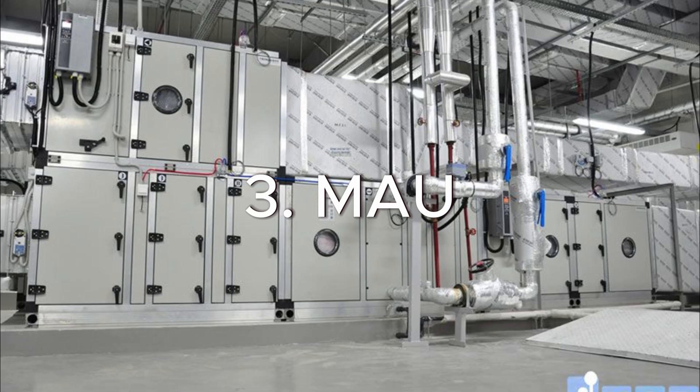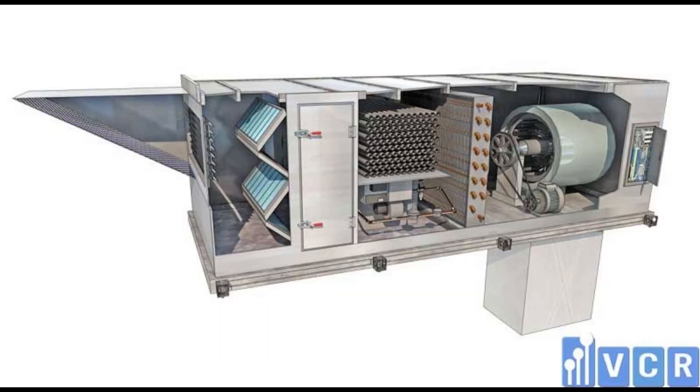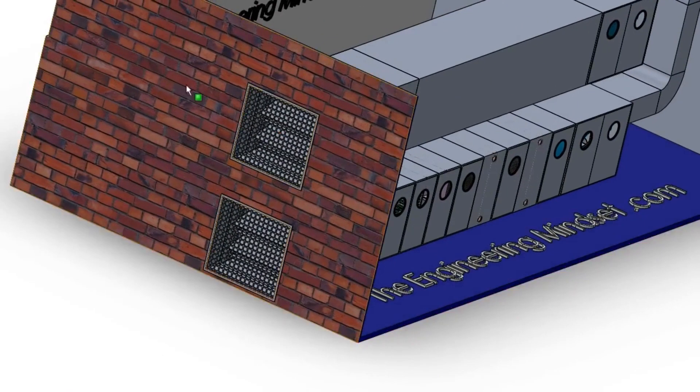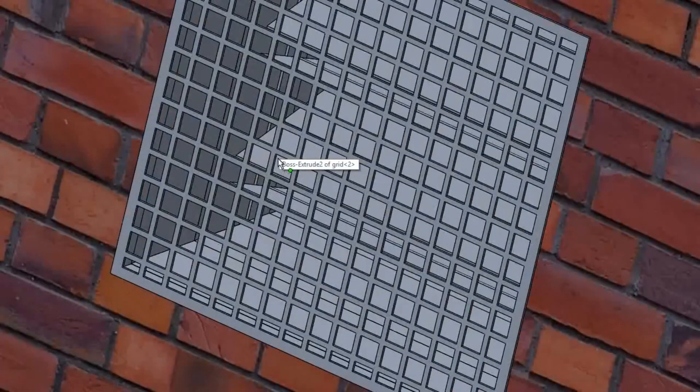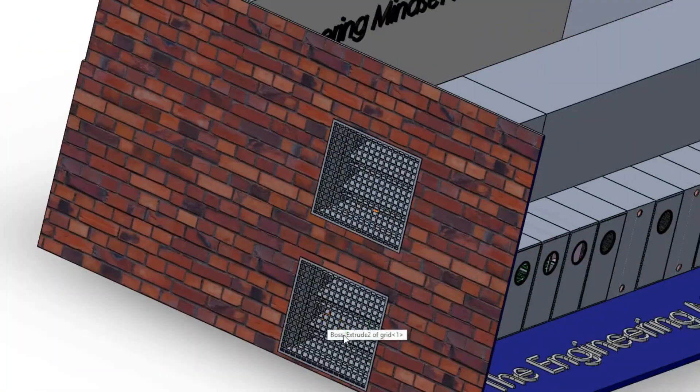Lastly is MAU, short for Makeup Air Unit, which is used in laboratories and areas with potential air contaminants, viruses, and other harmful substances. It exhausts a significant amount of air from the room to prevent cross-contamination and potential health hazards to personnel working in the area. This unit supplies 100% fresh air to the room and removes most of the air inside.